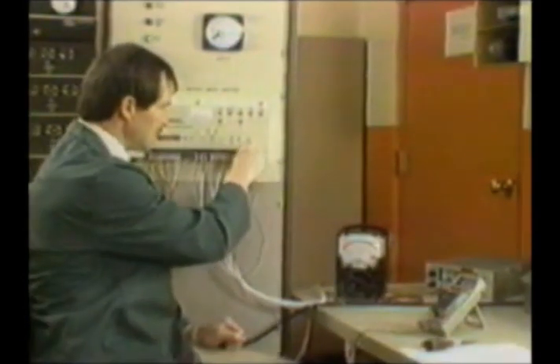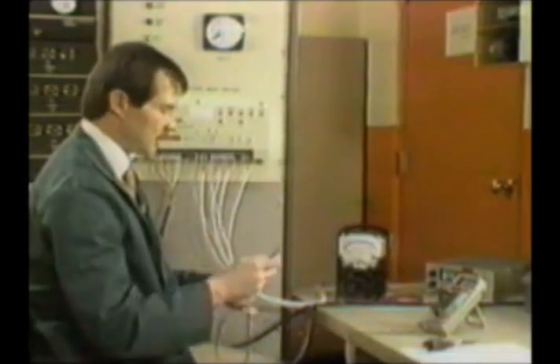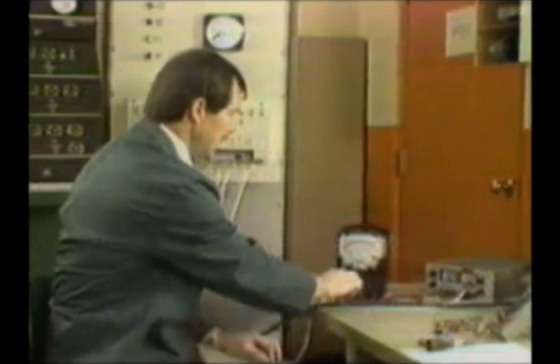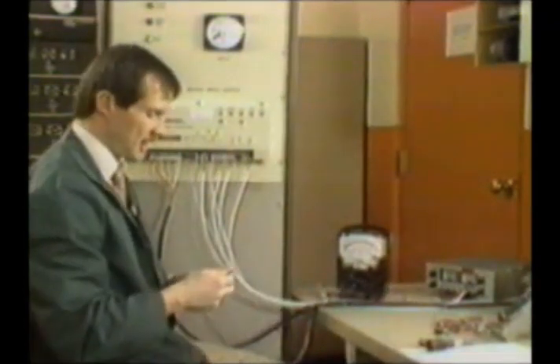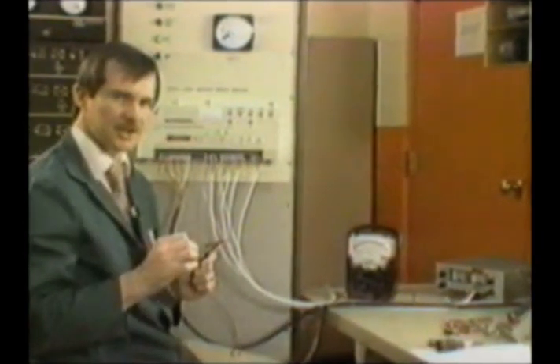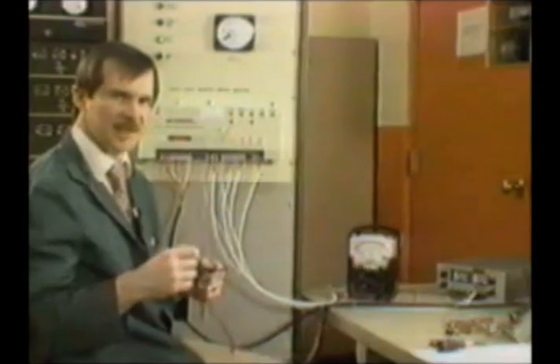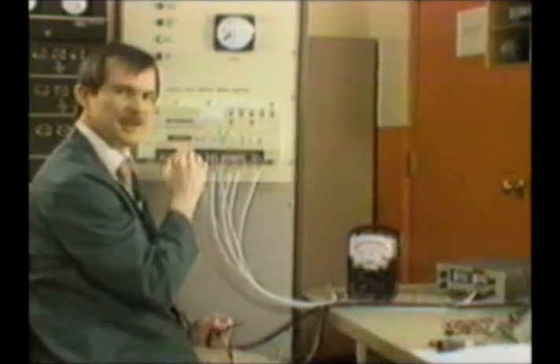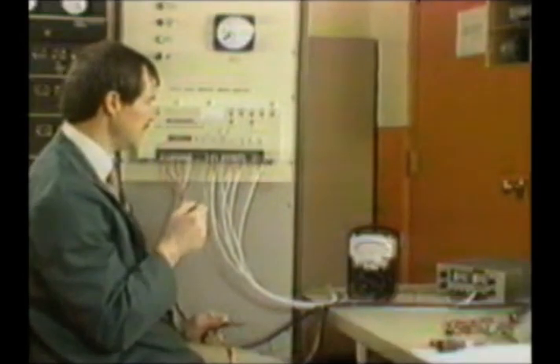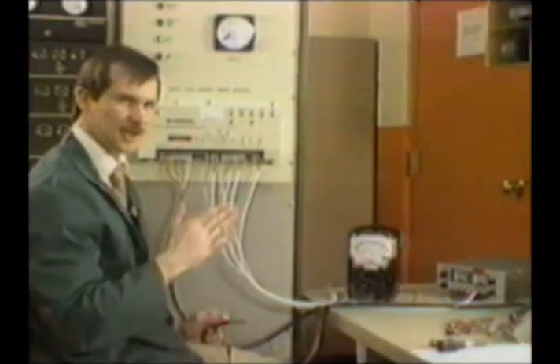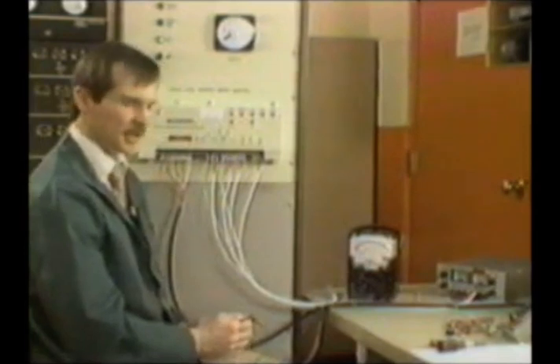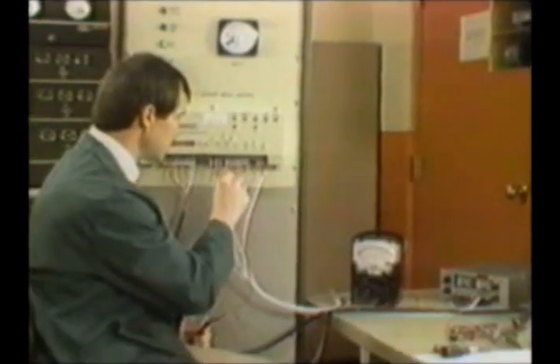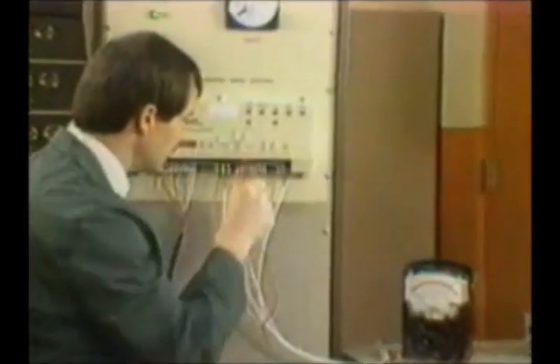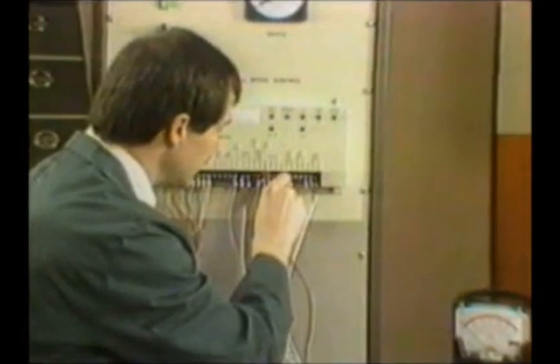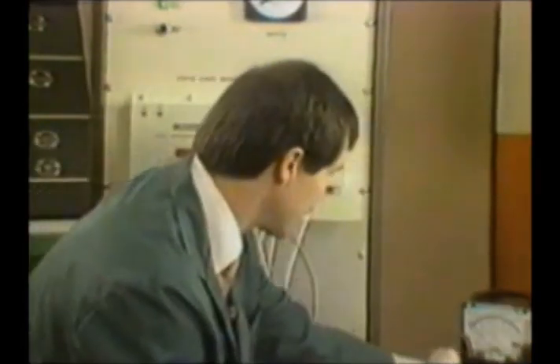So now I'm going to unhook my meter. I'm going to connect up my analog meter. My analog meter I'm going to connect up to my actuator voltage. The main thing here is once I get started, there's a good chance I'll be unstable. I'm going to have to adjust my gain and my reset potentiometers to adjust that instability out. And by using your analog meter, you can adjust it till you get the meter smooth. It's easier than looking at a Hertz meter or trying to listen to the engine and smooth it out. So let me go terminal 20 positive and terminal 21. You can see we're reading 0 volts on the meter.